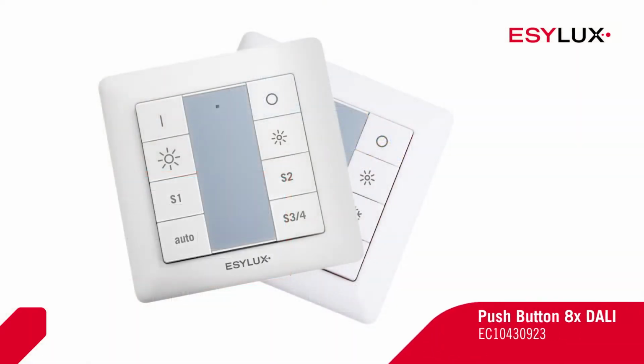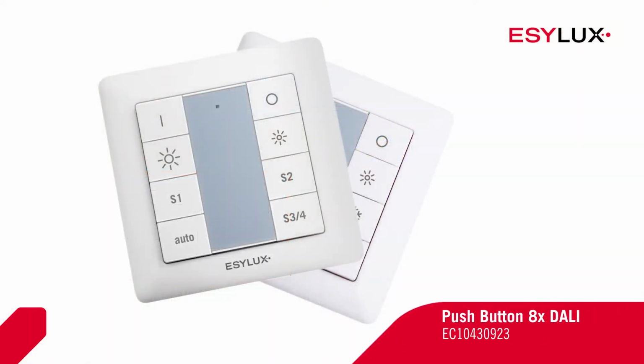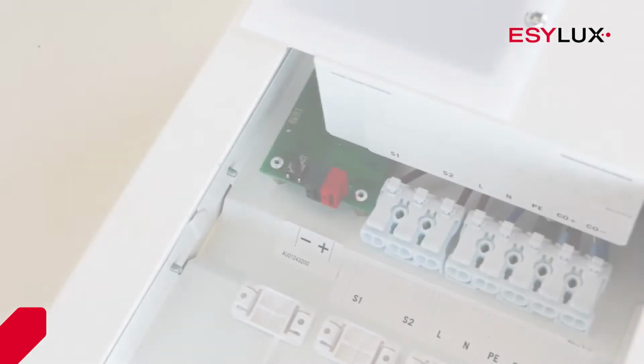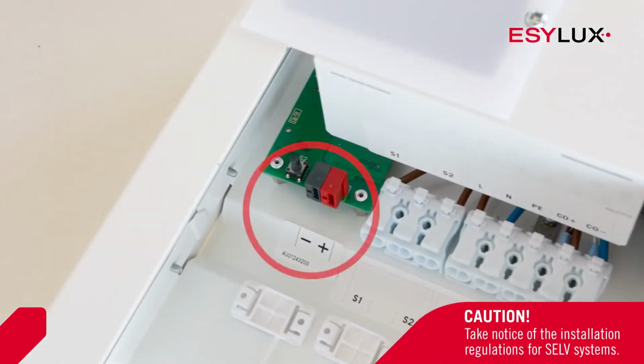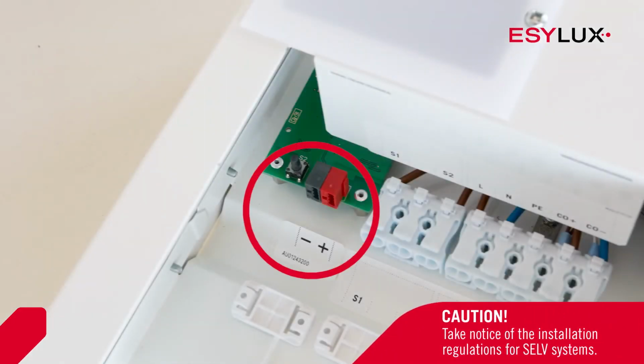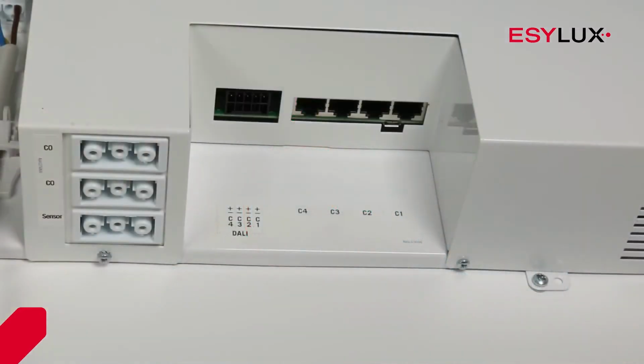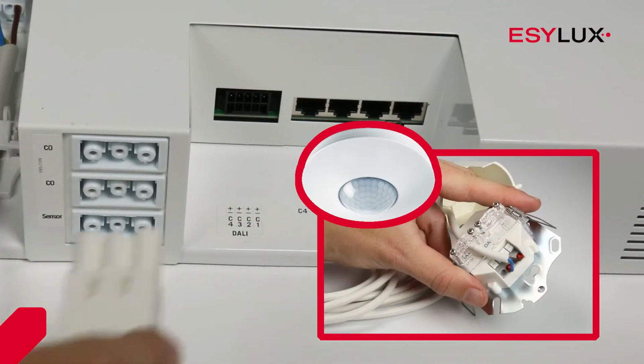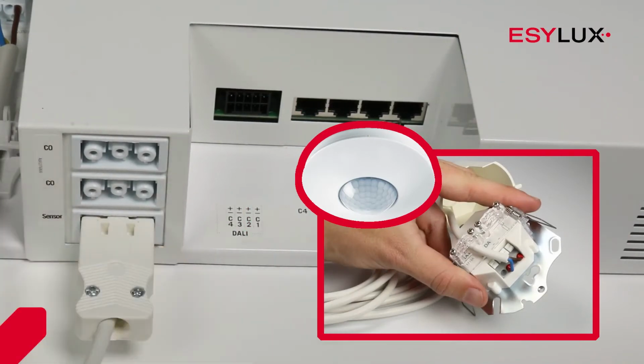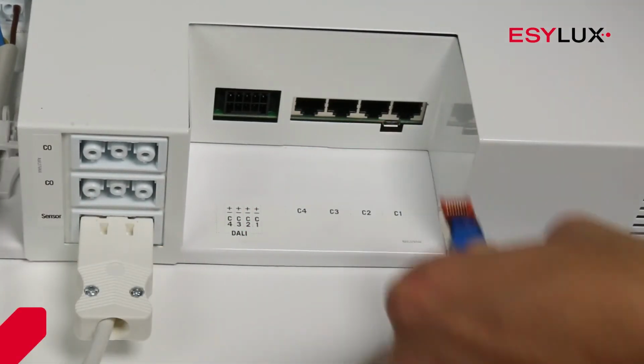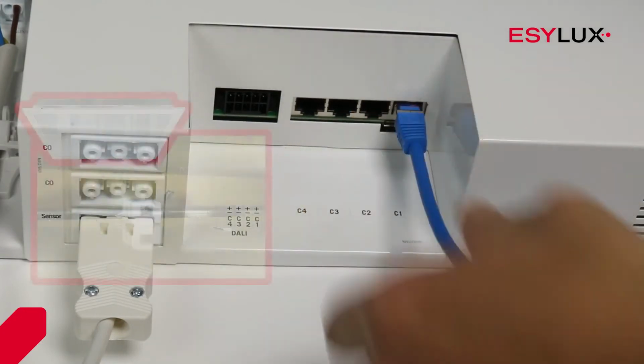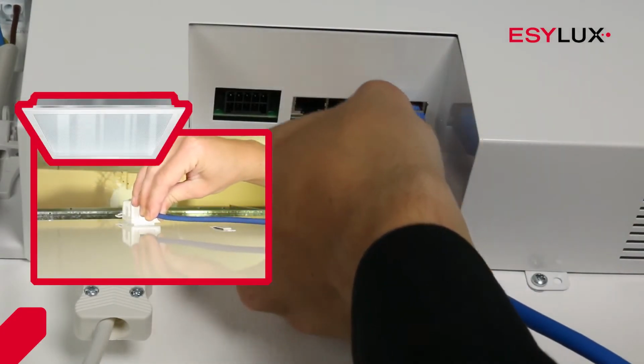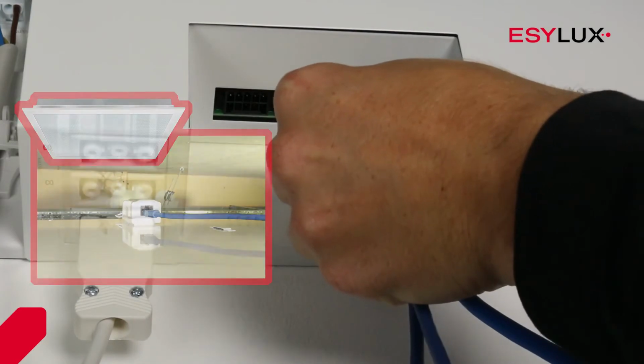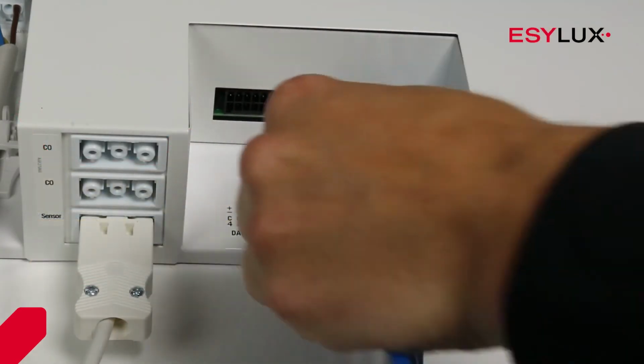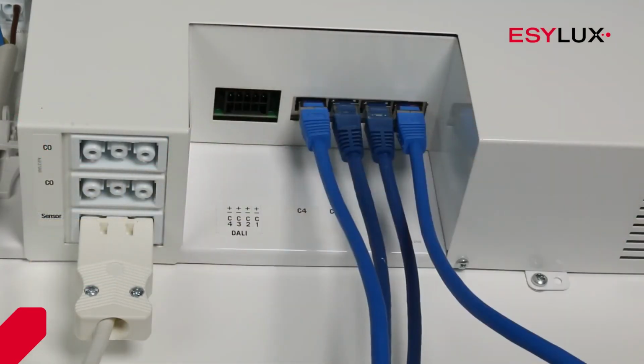Our intuitive Dali buttons are also practical. If you are using a KNX variant, you can network the SmartDriver with the KNX bus via the left-hand socket. It is very easy to connect the presence detector via the sensor interface. The lights are connected to the SmartDriver using the RJ45 cables. The RJ45 interfaces are assigned channels that the SmartDriver can control separately.